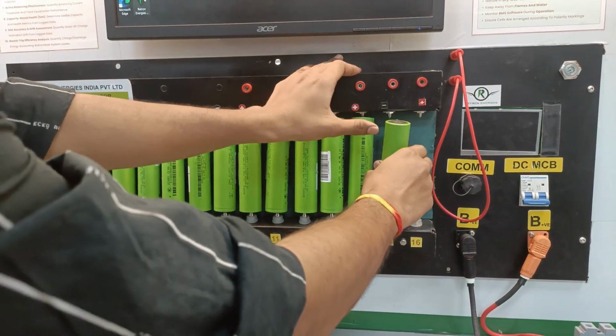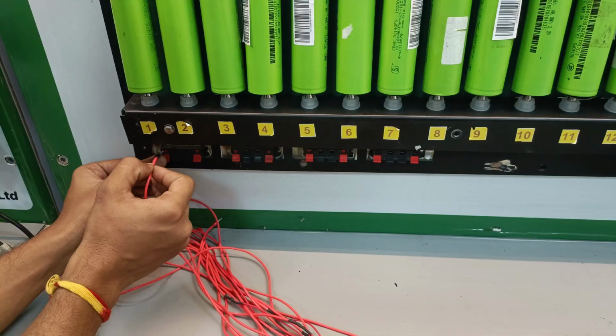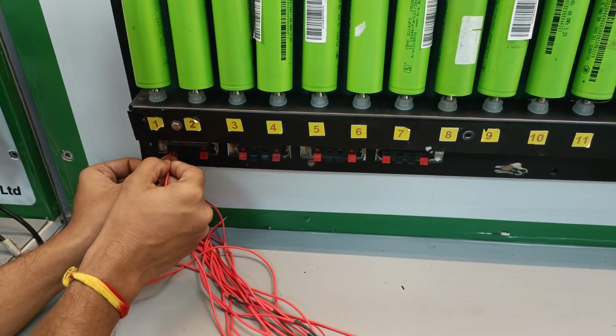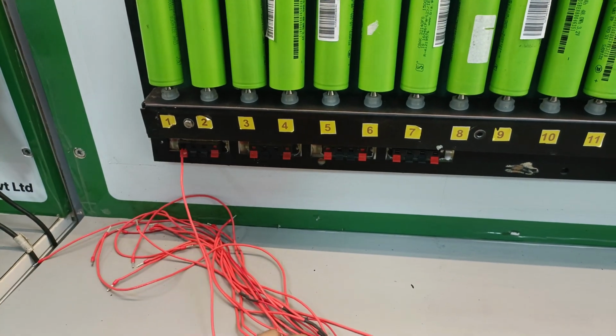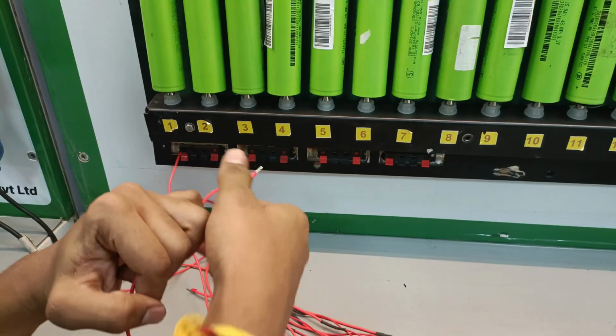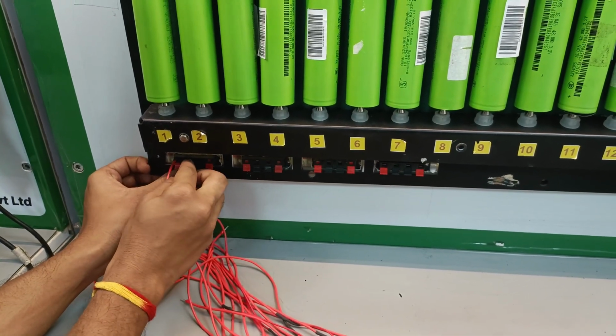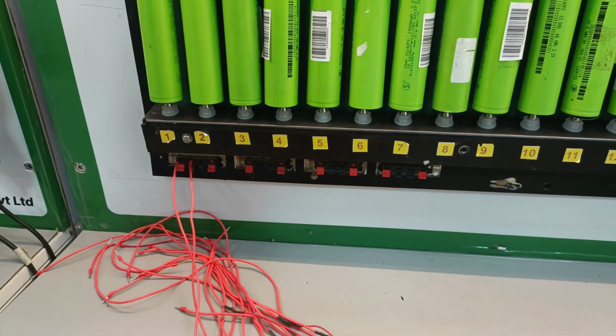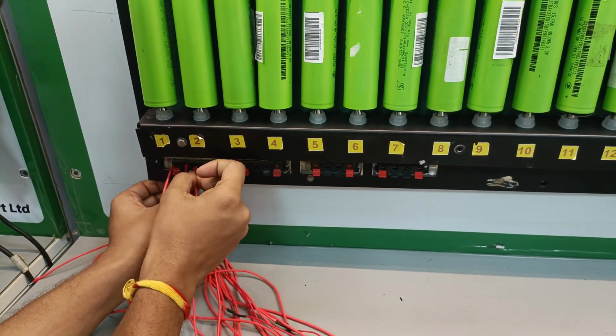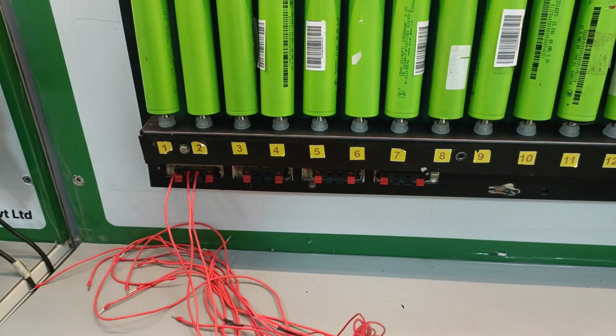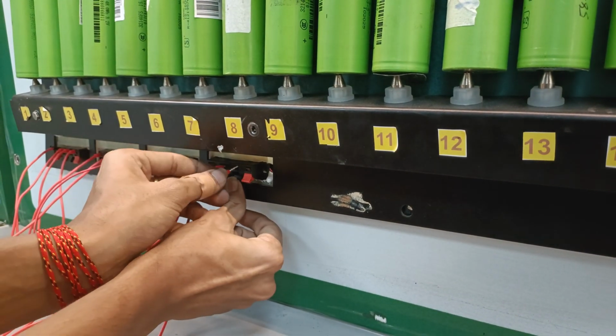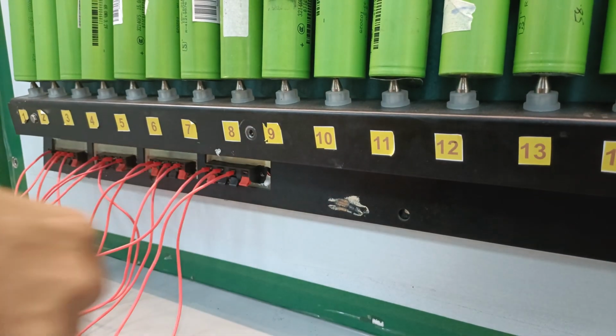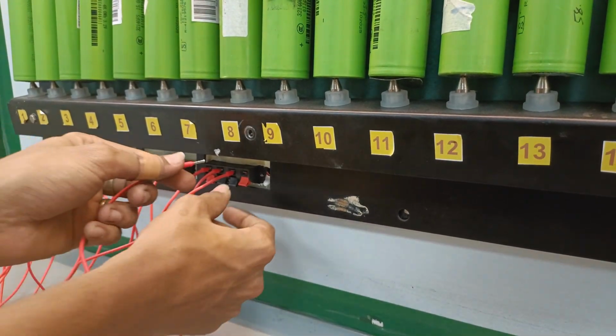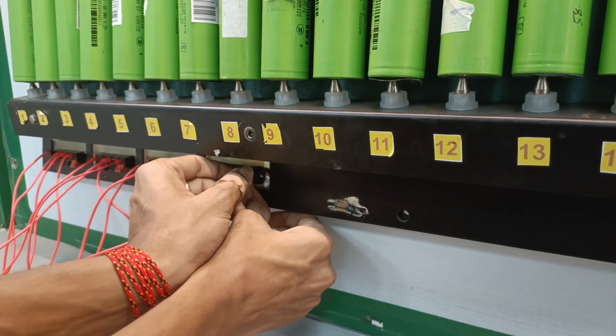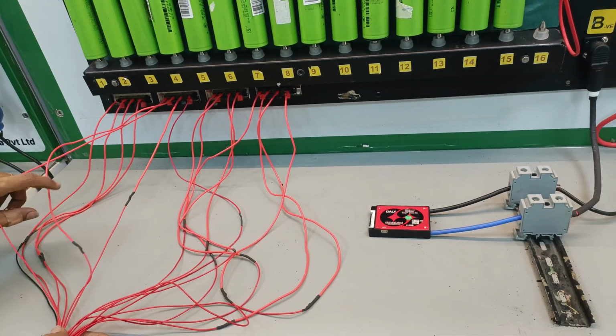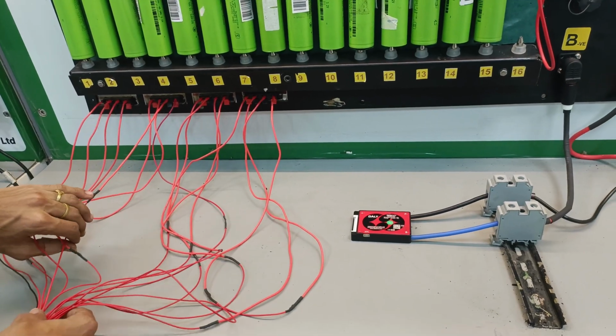After placing all the cells, the next step is to connect the battery management system to the battery pack. To do this, connect the BMS sensing wires to the cell push button terminals provided on the battery pack emulator. First, connect the black sensing wire, also known as the B0 wire, to the negative terminal of the first cell. Then connect the remaining sensing wires sequentially according to the cell arrangement until all cell connections are completed. It is very important to follow the correct sequence while connecting the sensing wires. Once all connections are completed, carefully cross-check each sensing wire to ensure proper connectivity and accurate voltage measurement.